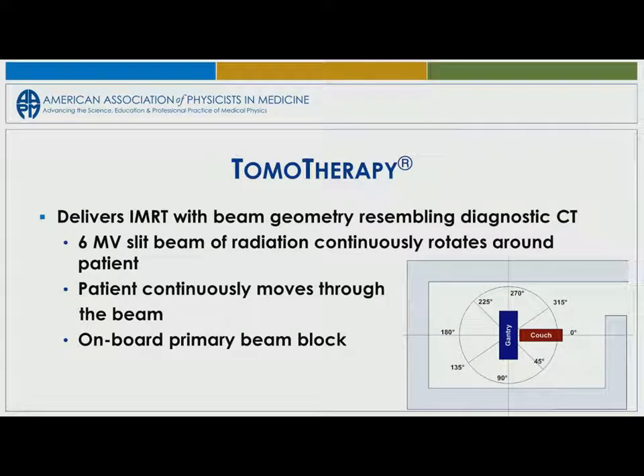You only have 6 MV, which the nice part is, how can you shield with 6 MV? If you want to do that, you can add lead brick. You don't have to worry about neutrons. So we have places that put tomotherapy units in because that's sometimes the only thing that'll fit in the room. If you don't have room above your ceiling, they'll put in a tomotherapy unit.